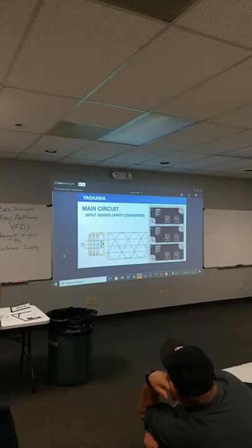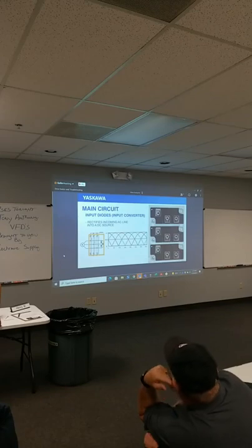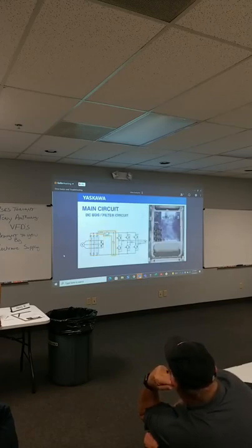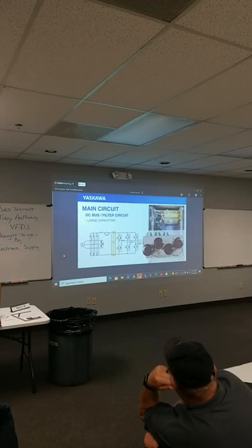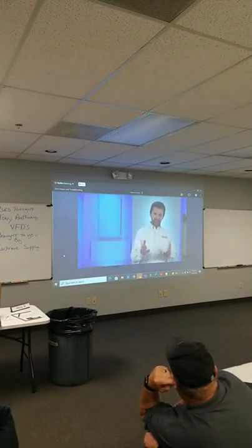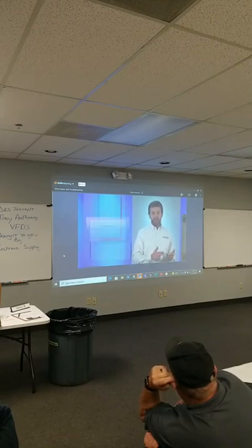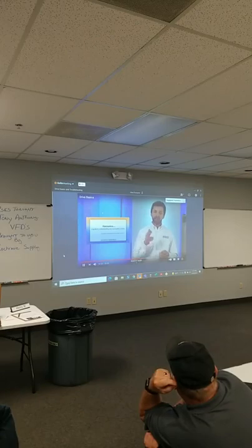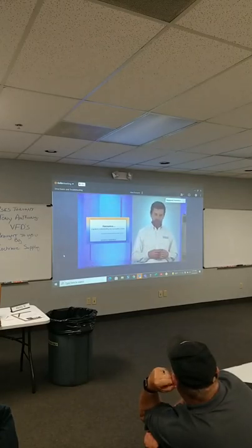Most drives today perform a full wave rectification, which means these diodes chop the AC line and create a DC supply. That is the first of the three major components in the drive. The voltage output from the rectifier is then refined by a filter circuit consisting of large capacitors and, in some cases, a DC link choke. In any system using a combination of a rectifier and a filter, capacitors may result in discontinuous current draw. Now, this results in harmonics being reflected back on the incoming line. Yaskawa has a video titled Harmonics that further explains this topic and ways to mitigate harmonics.